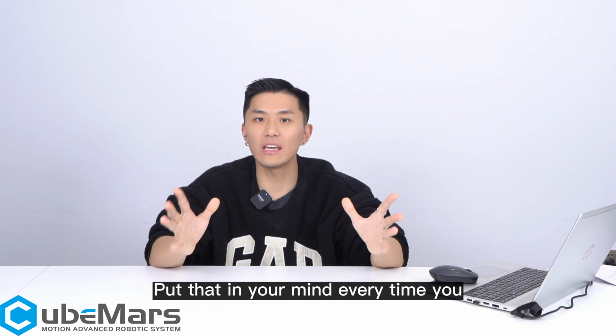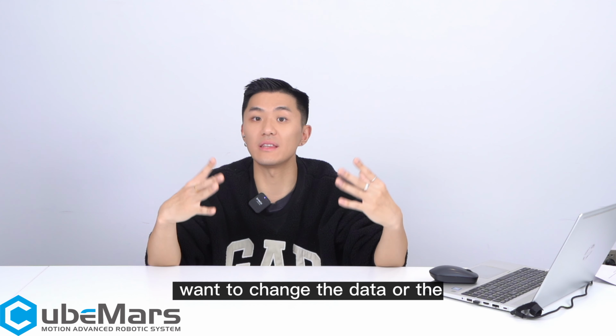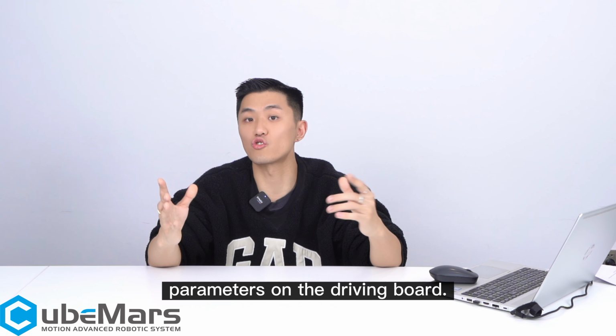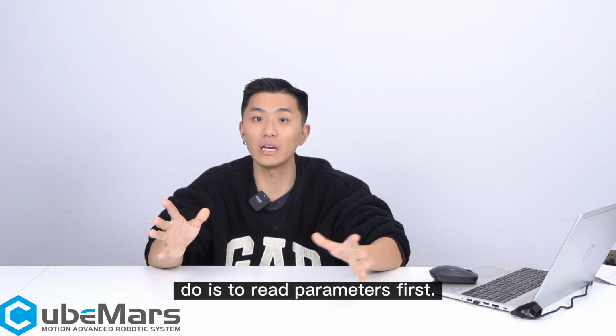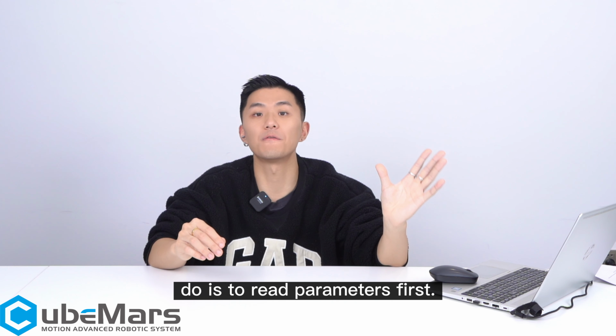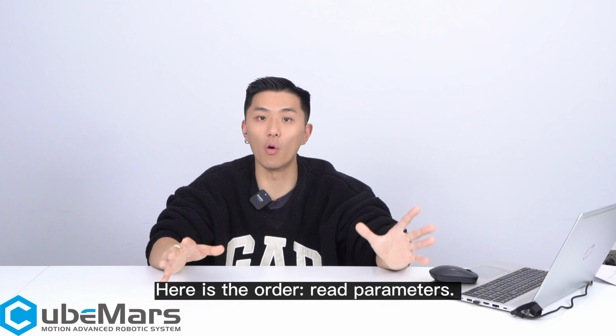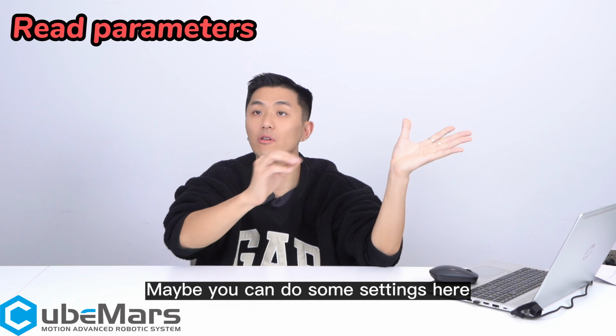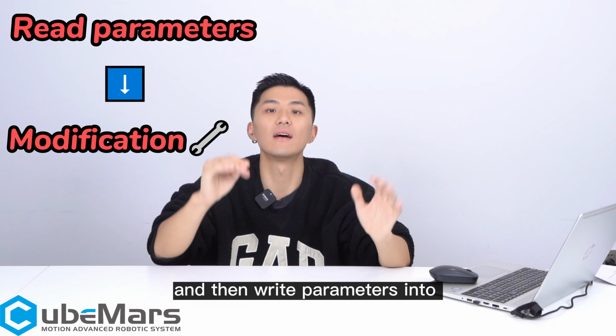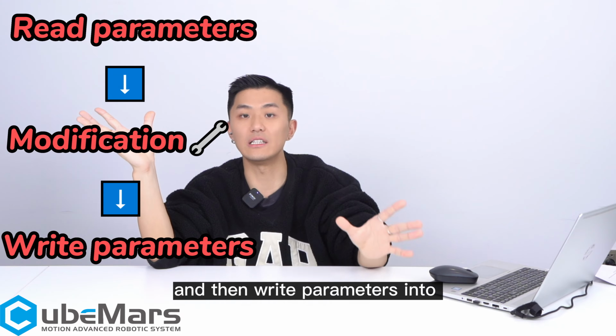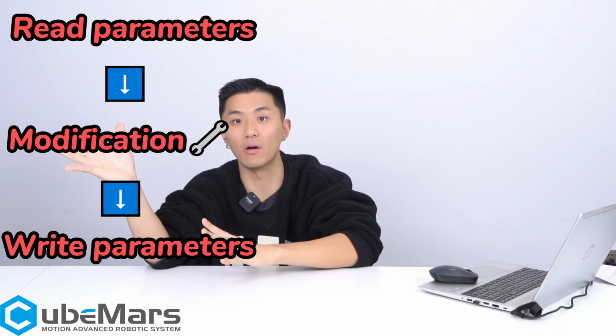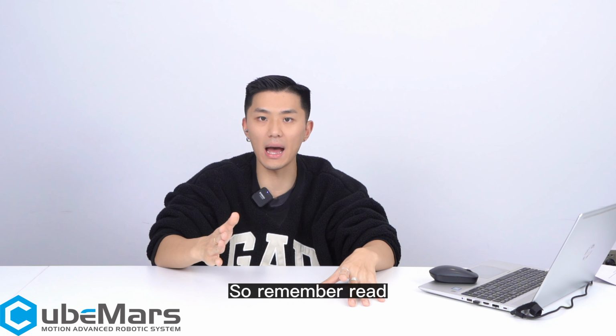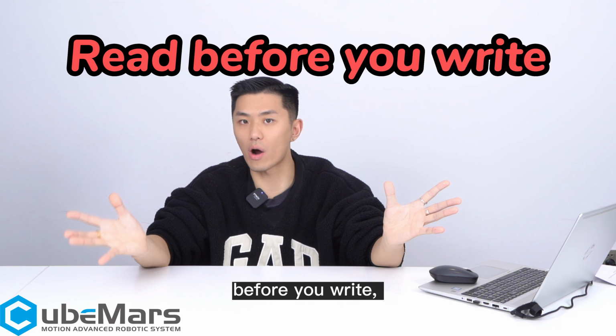So put that in your mind. Every time you want to change the data or the parameters on the driving board, the first thing you need to do is to read parameters first. So here is the order. Read parameters, maybe you can do some settings here, and then write parameters into the driving board of the motor. Okay, that is the order. So remember, read before you write.